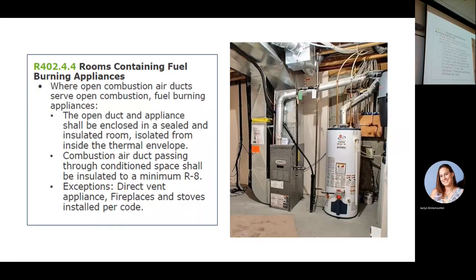Which takes us to the next thing. An 80% efficient furnace is what we call a natural draft furnace, or a fan-induced furnace, which means it draws combustion air from the space. A natural draft water heater has a little diverter on it. It's like heating a pot on the stove, but we have an opening up the center so the products of combustion can come up, and it draws some other air from inside the space and takes it up the vent. A B vent is a natural, non-positive vent system.